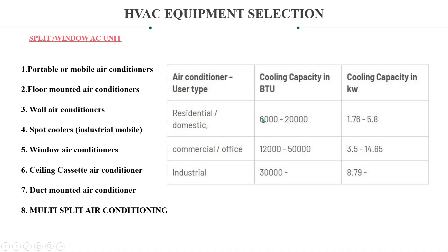Cooling capacity in BTU — 12,000 BTU per hour is equivalent to 1 ton of refrigeration. For residential and domestic applications, we mostly use 6,000 to 20,000 BTUs. For commercial and office applications, we use 12,000 to 50,000 BTUs. For industrial applications, 30,000 BTUs is a starting point. These are the equivalent values in kilowatts.